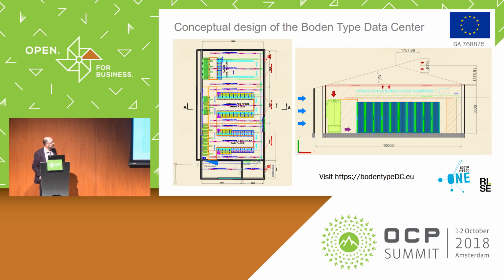In the winter, we will probably recirculate almost the majority of the heat to keep the air at an appropriate temperature for the servers. Obviously, if you do that, your humidity will drop, so we have to use some wet pads to humidify the air when it comes in.